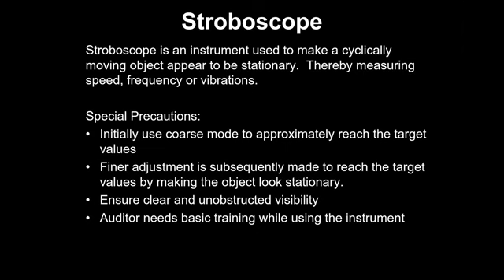Basically, it emits light at a certain frequency, which can be adjusted. When you adjust the frequency, you will see that the rotating object is actually stationary. So we adjust the emitting frequency such that the rotating object appears to be stationary, and that is the RPM. So you can do it very comfortably and there's no problem on that.